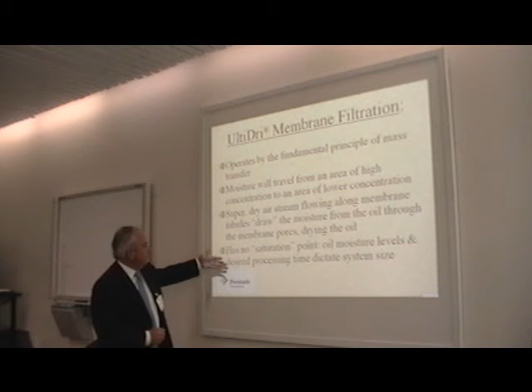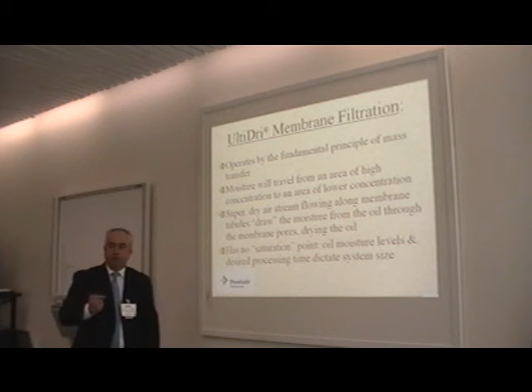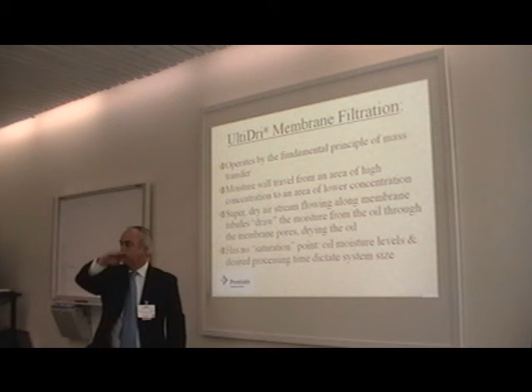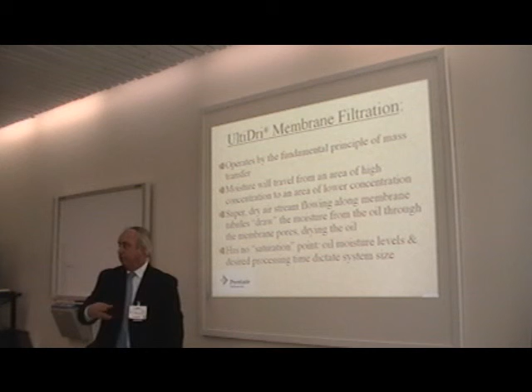One interesting thing is the saturation point we talked about earlier—there's no concern with that here. Essentially, the greater the differential between the moisture in the air and the moisture in the oil, the greater the rate of exchange. That's why with a system that upsets periodically, like the example of that other power plant where they change load, the rate of water removal is 10 times higher right after loading up than it is once it gets back down to 100 ppm. So it goes up with the concentration.